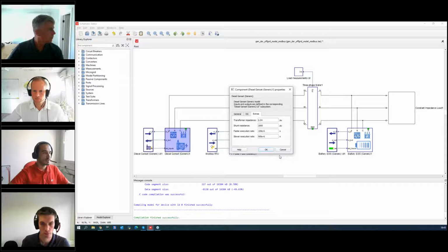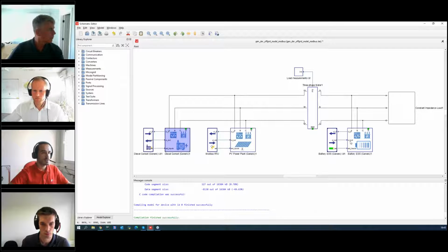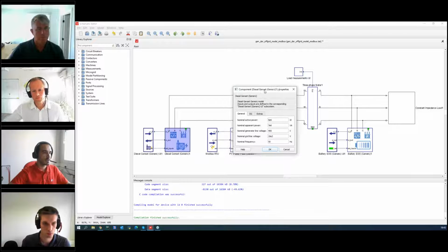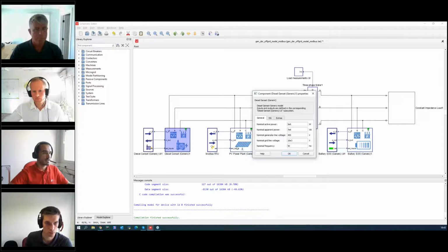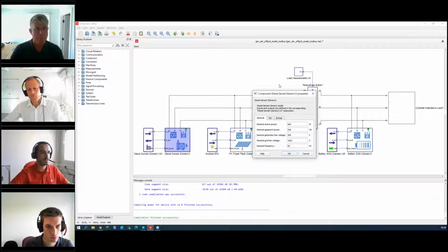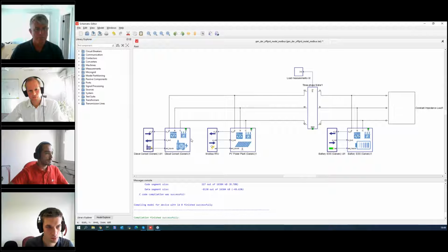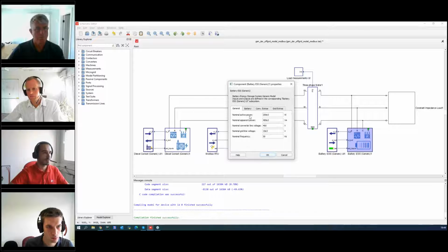Also interesting, all of these DRs have embedded transformers. For example, in this case, the nominal generator line voltage is 400 volts, but we are boosting that to 10 kV, so this line here is all 10 kV. A similar story applies to the other DRs.